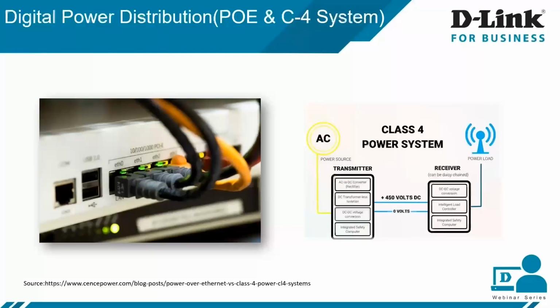Now we know some basics of power over Ethernet, which is a DC power distribution system, and also the class 4 system, which is also a DC power distribution system. We've already discussed why we want DC power distribution - to cut off the energy wasted converting AC into DC. We wanted a proper mechanism, and one we're already using is power over Ethernet - type 1, type 2, type 3, type 4. This class 4 rating was very recently added in 2023.